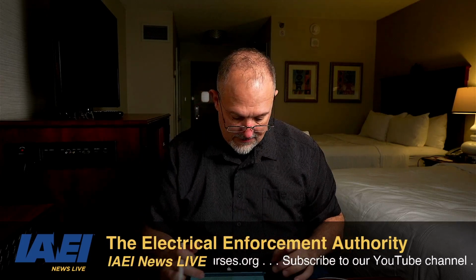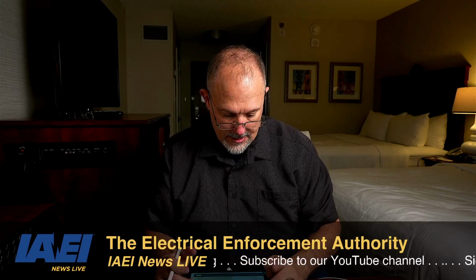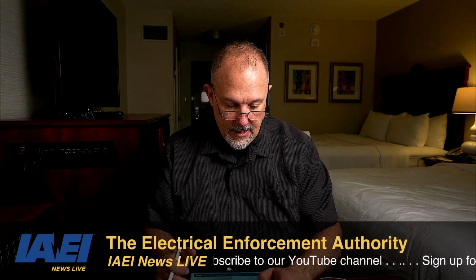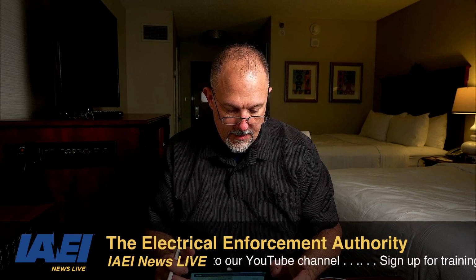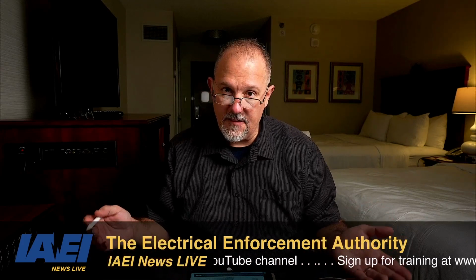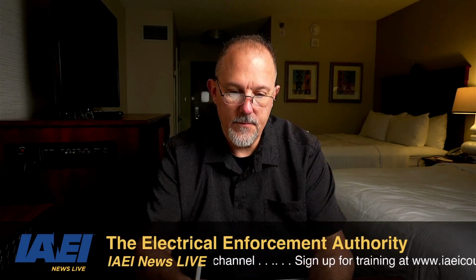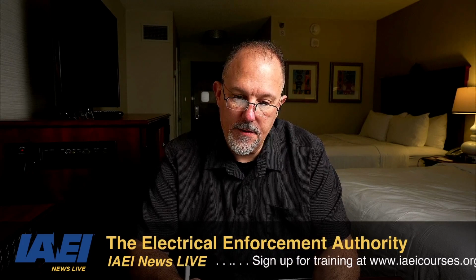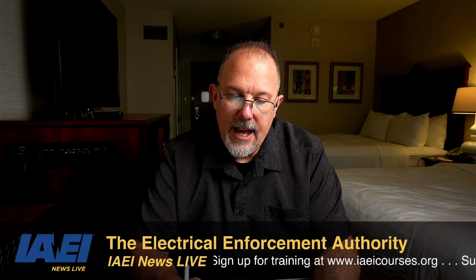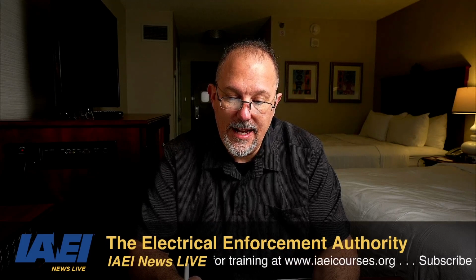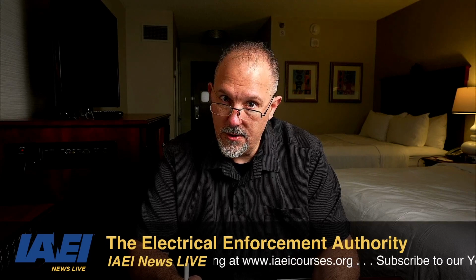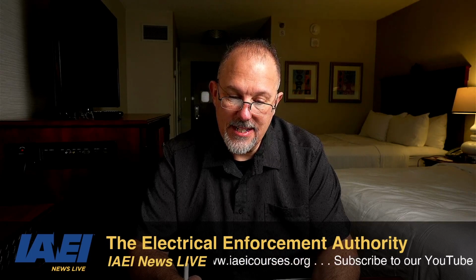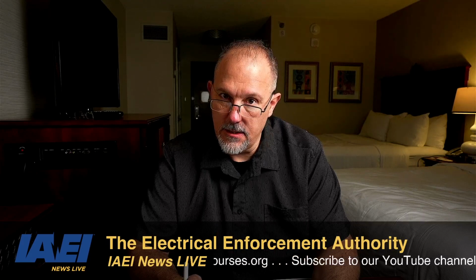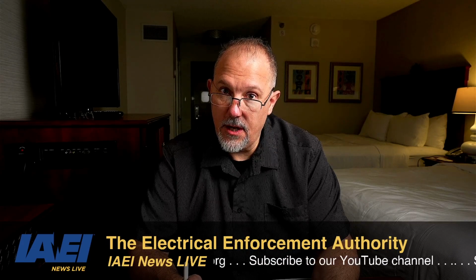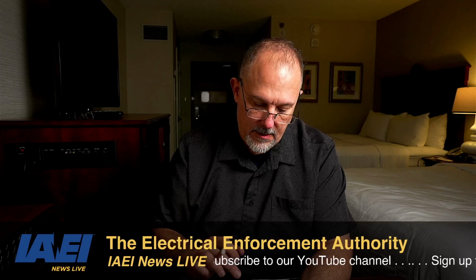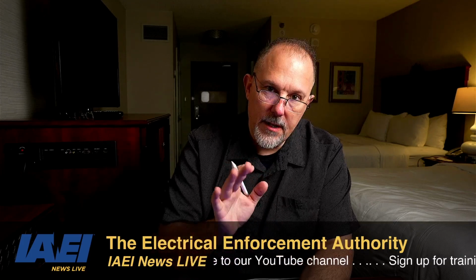What is a separately derived system? Well, we're still in Article 100, and we're going to take a look for the definition of separately derived system. There it is. I can't give you a page number because I'm on NFPA LiNK. An electrical power supply output other than a service having no direct connections to circuit conductors of any other electrical source other than those established by grounding and bonding connections.